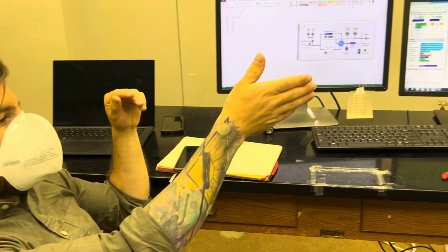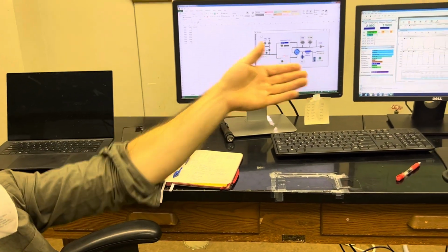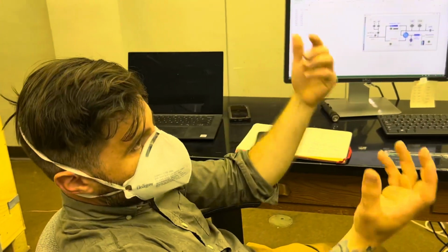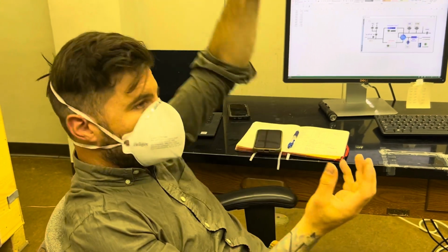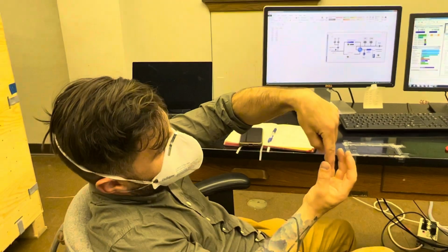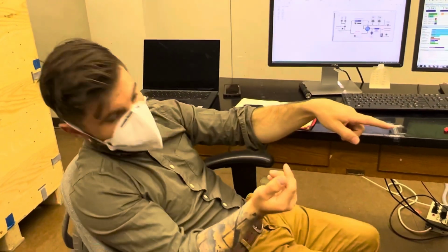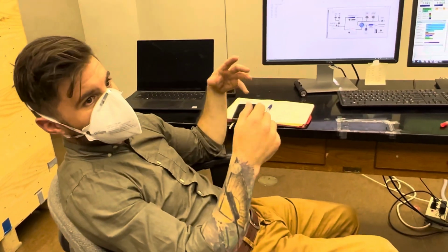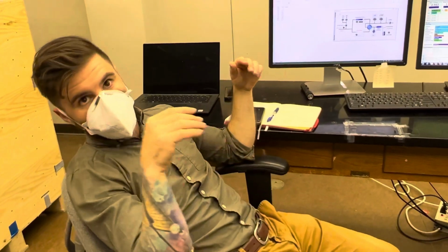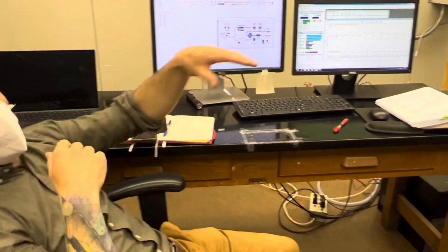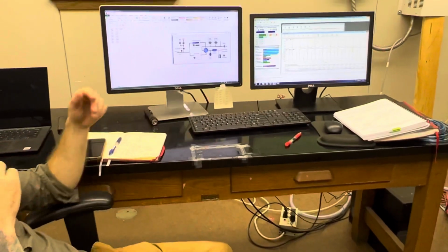Because the gas is coming out of the cylinder and going into the conflow, and it's constantly flowing into an open cup pretty much, and the capillary comes down to sniff that, and then brings the gas into the source. When it's in the source, not all that gas is actually ionized and brought through. So some of it is not ionized, but everything that makes it to the cup is ionized. Otherwise, it would never get picked up by the magnet current to get there.